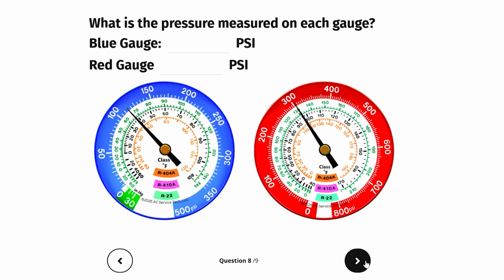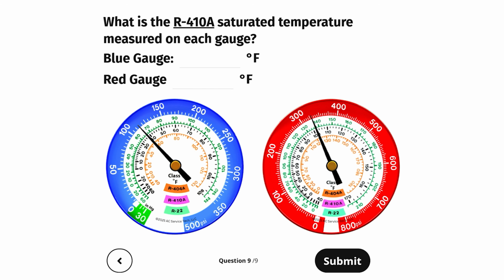What is the pressure measured on each gauge? So on the blue gauge, we look at the outer ring, and each little increment is 5 psi increments. So we look at the 100 plus 1, 2, and the third increment, and so we know it's 115 psi. Now on the red gauge, once again, we look at the outer pressure ring, and those, once again, are in 5 psi increments. So we're at 305 psi. Now on to our next question.